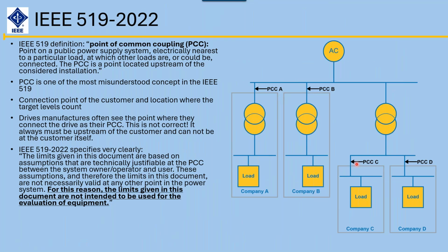Companies C and D, they're meeting down here. So this is their point of common coupling, okay? So this is what I don't like about the standard: the standard is only referencing everything to the point of common coupling. All the consultant engineers I work with say this drive must comply to IEEE 519, but they're talking some point down here. The standard doesn't tell me what to do down here. The standard only tells me what to do up here.